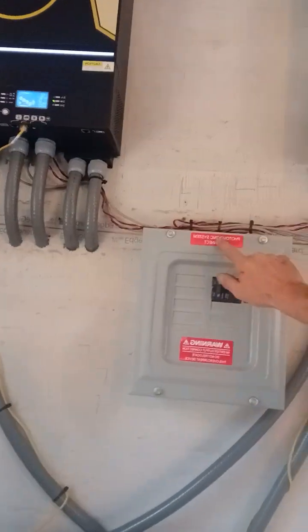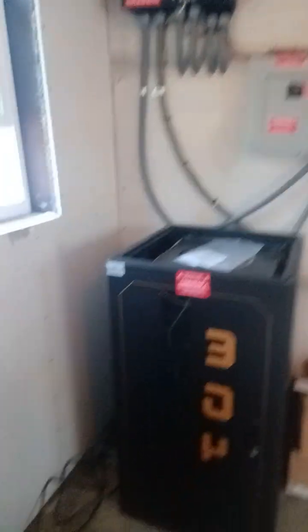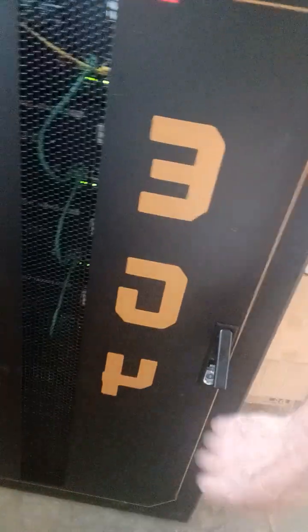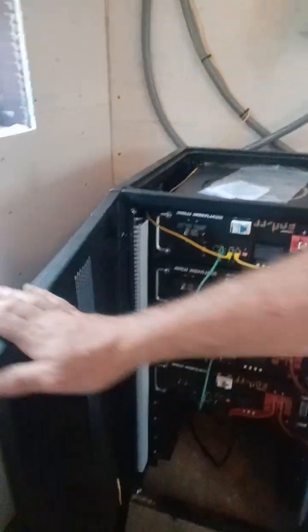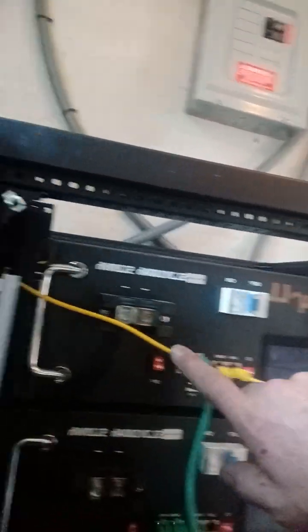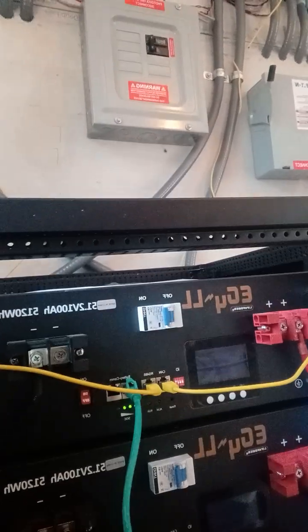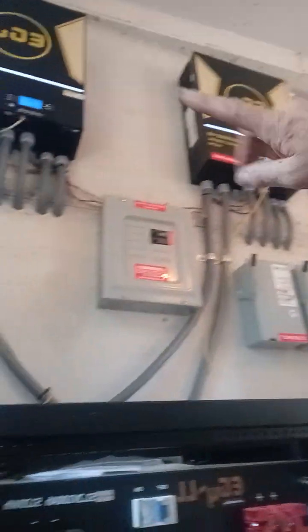As you can tell, everything's labeled, tagged, and up to code here for DC disconnects. They bought the battery cabinet but didn't have a door, so we went ahead and supplied them with that door. There are four EG4 5.12kWh lithium iron phosphate batteries. These are the BMS communication cables — the yellow cable goes up to the inverter on each one. Technically you only need one, but we like to have the secondary one as well.